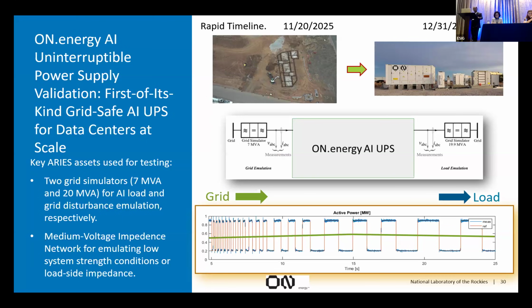We have some exciting results coming out, but these are some preliminary results I want to show. The oscillating curve is the power coming out of the data center, and the green is the power going into the grid. The UPS has storage embedded in it that can produce very smooth curves into the grid, and can also take care of grid disturbances so that data centers don't see them. This UPS is capable of eliminating or decoupling disturbances on both sides of the system.